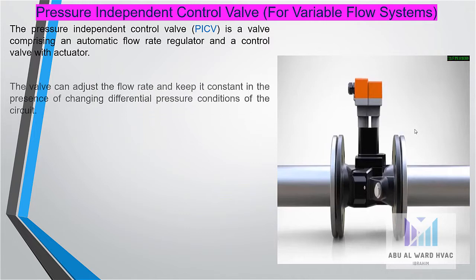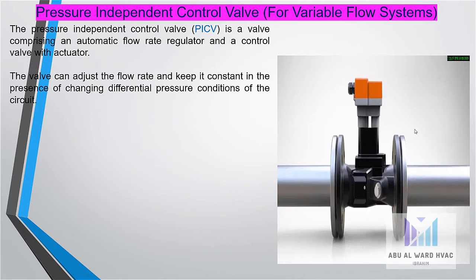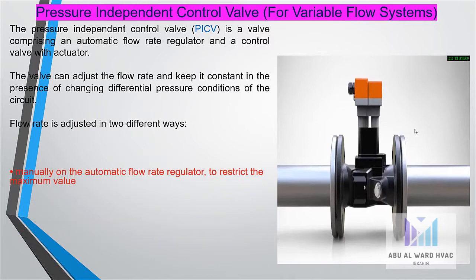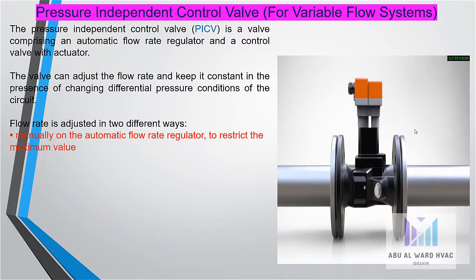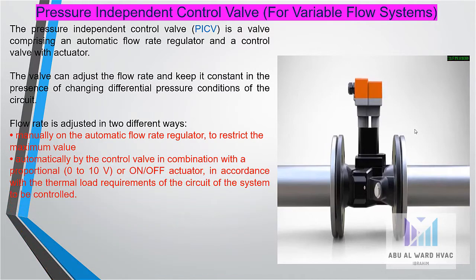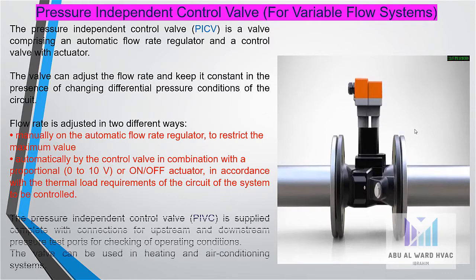The pressure independent control valve PICV is a valve comprising an automatic flow rate regulator and a control valve with actuator. The valve can adjust the flow rate and keep it constant in the presence of changing differential pressure conditions of the circuit. Flow rate is adjusted in 2 different ways: manually on the automatic flow rate regulator to restrict the maximum value, and automatically by the control valve in combination with a proportional 0 to 10 volt or on-off actuator, in accordance with the thermal load requirement of the circuit of the system to be controlled.